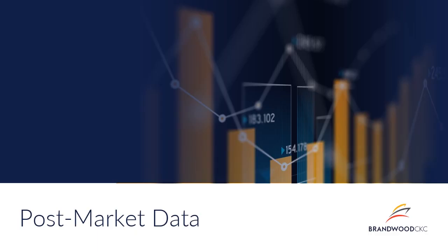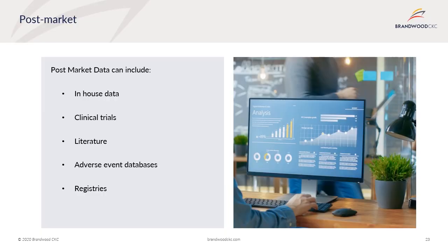So our last key aspect, we'll talk about post-market data. Post-market data can be a combination of the in-house data, which is basically everything that's held by the manufacturer, so adverse events, complaints, as well as recalls and corrective actions. It can also include data from external sources, so registries, publicly available adverse event databases, recall databases, and clinical trial databases.